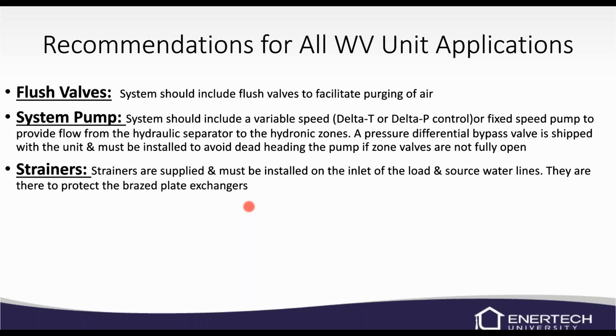The system pump, so the zone pumping, I would recommend a variable speed pump. You can use a fixed speed pump to provide pumping on the secondary side. You will also need a pressure differential bypass that you'll need to install to avoid deadheading that pump. Strainers are supplied and they must be installed on the inlet of the load and source water lines. Just make sure that you're always installing strainers on the source and the load. They're supplied with the unit. It's not an option.